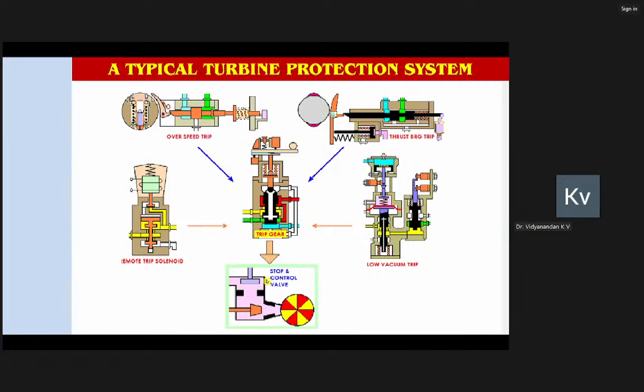With the trip oil only, stop valves remain open, control valves remain open, and this device is linked with all the master tripping devices. It could be mechanical design, or hydraulic, or only electronic. In your classical design, like in your 250 megawatt, you have overspeed mechanical, low vacuum mechanical, thrust bearing mechanical, etc. Whereas in the latest case, overspeed or low vacuum or axial shift, everything is in electronic form. If you have only electrical, then that signal will be routed through a solenoid. That is what we call the remote trip solenoid. It is basically a binary logic, either energized or de-energized, and it will simply cut off the oil supply going to the trip gear.